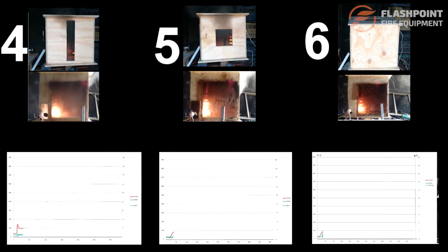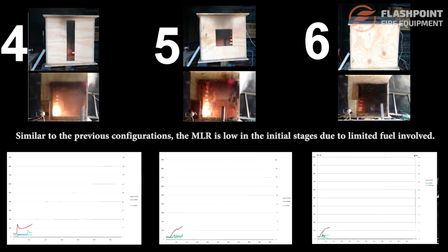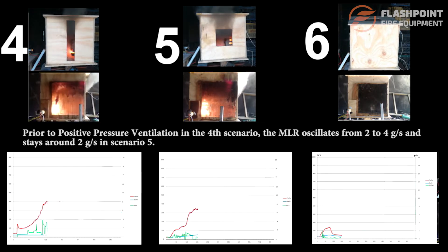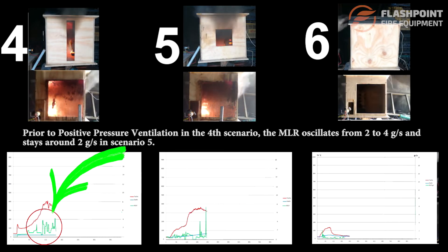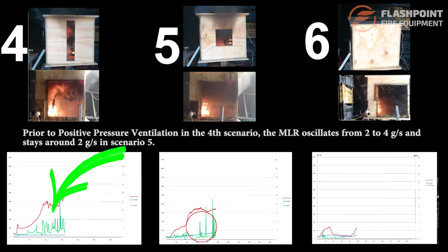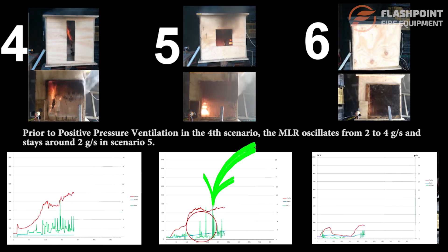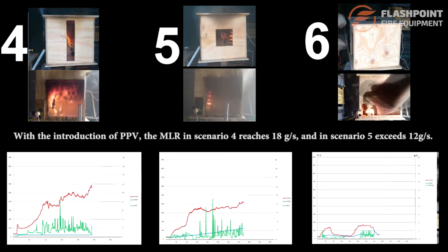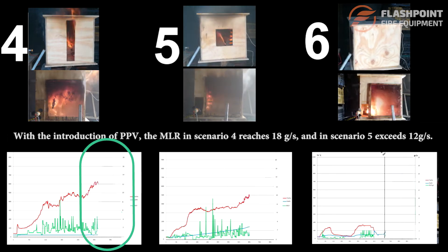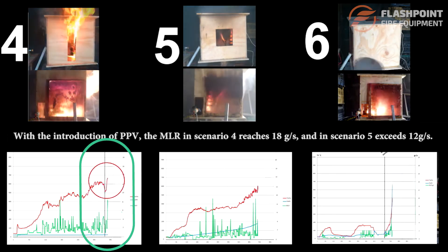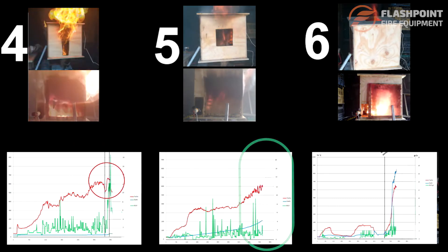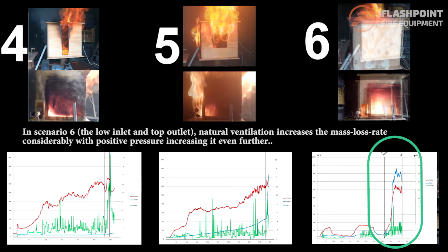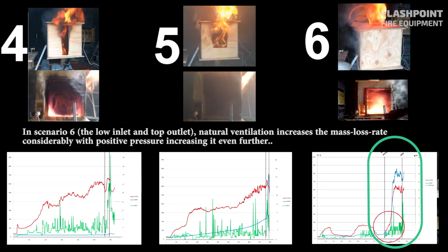Comparing the second series of test configurations, we find similar results at the initial stages as the mass loss rate is limited by the small amount of fuel involved. Prior to the introduction of positive pressure ventilation, the mass loss rate in scenario 4, the vertical opening, oscillates between 2 to 4 grams per second and hovers around 2 grams per second in scenario 5. With the introduction of positive pressure ventilation, the mass loss rate in scenario 4 reaches 18 grams per second and in scenario 5 exceeds 12 grams per second. In scenario 6, the low inlet and top outlet, natural ventilation increases the mass loss rate considerably, with positive pressure increasing it even further.